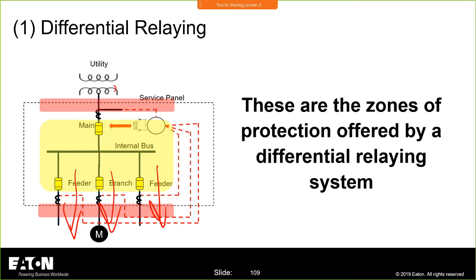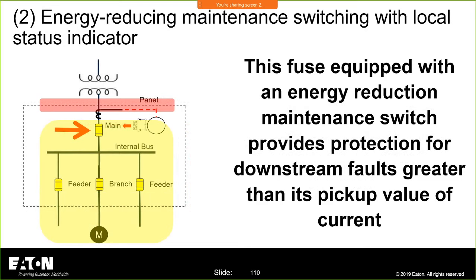There are CTs at the top and the bottom of these drawings. That's a current transformer. This is a current transformer. Anything that's going into that zone has to be accounted for when it goes out of that zone. And this relay will tell you when the current going in doesn't equal the current going out. So that's how differential relaying works. It doesn't recognize any faults downstream. The energy reduction maintenance switch, since it's just based on current value, will look as far downstream as the impedance in the system will let it look. But it basically will shunt trip a switch and open that circuit for faults downstream.